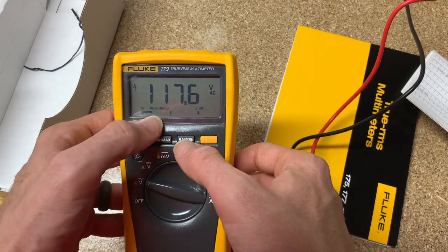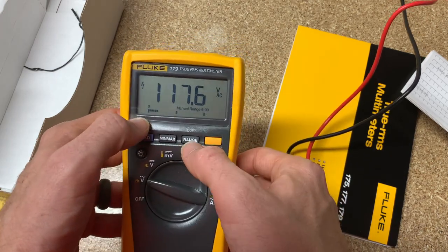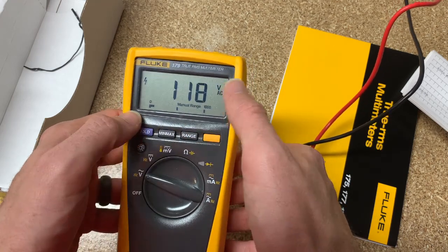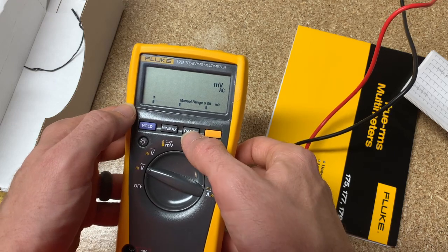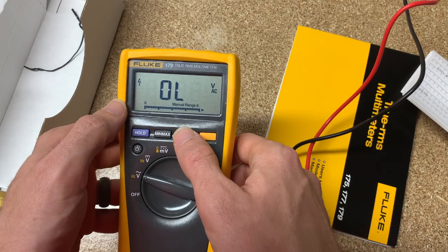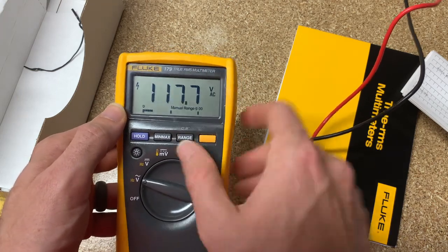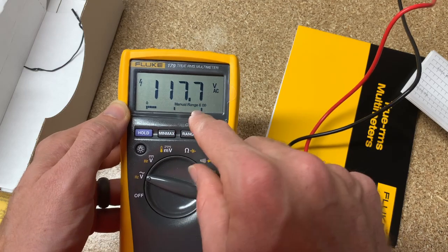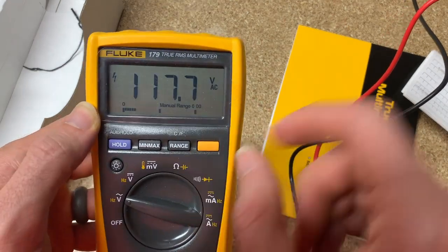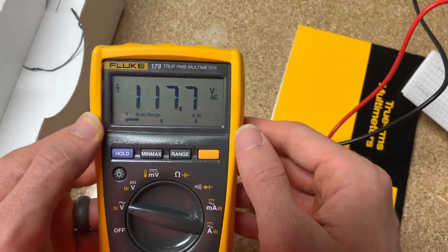We can hit range if we want to change this range. So now we're in auto ranging. But if we hit range, manual range, we can start changing this to where it just goes to 118. Stays there, right? Millivolt, obviously out of limit for all these ranges. And then you get back to where we were when we first started with the auto range. You want to go back to auto range after you've been in manual. Just hold this range button down for a couple seconds. It'll go back to auto and you're good to go.